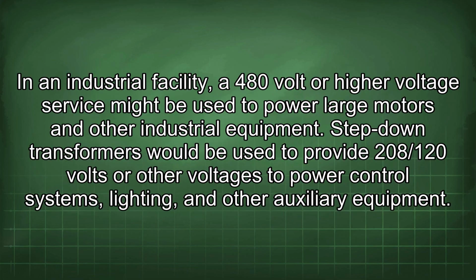In an industrial facility, a 480 volt or higher voltage service might be used to power large motors and other industrial equipment. Step-down transformers would be used to provide 208/120 volts or other voltages to power control systems, lighting, and other auxiliary equipment.